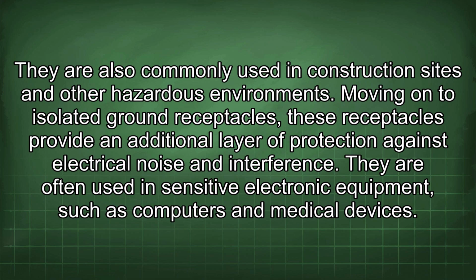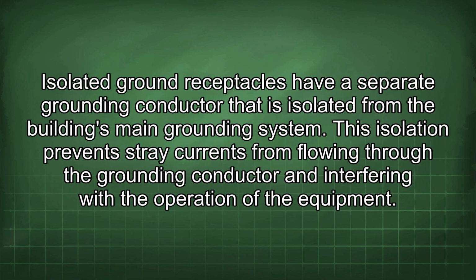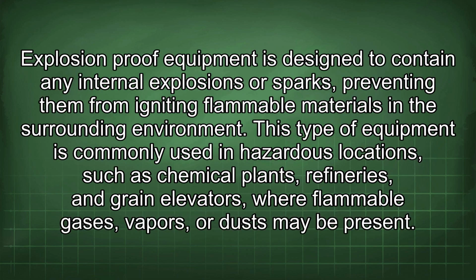Moving on to isolated ground receptacles. These receptacles provide an additional layer of protection against electrical noise and interference. They are often used in sensitive electronic equipment, such as computers and medical devices. Isolated ground receptacles have a separate grounding conductor that is isolated from the building's main grounding system. This isolation prevents stray currents from flowing through the grounding conductor and interfering with the operation of the equipment.